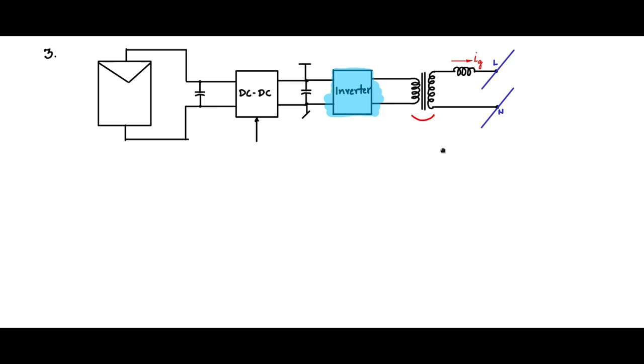This topology uses an inverter with an isolating transformer. However, this transformer is a low-frequency (LF) transformer because the currents and core flux are at 50 Hz, so it must be designed to handle 50 Hz flux. As a result, it will be big, bulky, expensive, and very heavy — which is a major disadvantage.